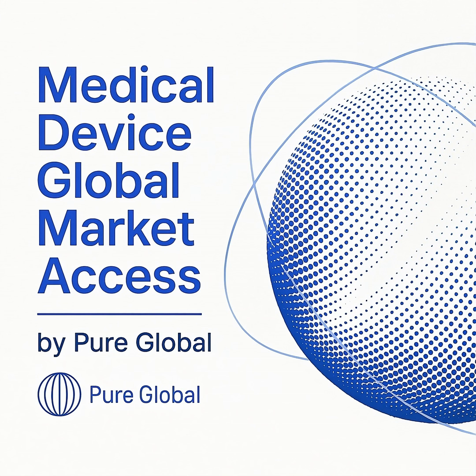Today we are focusing on a critical standard for any medical device manufacturer conducting human trials. ISO 14155-2020, which outlines the principles of good clinical practice, or GCP, for the clinical investigation of medical devices. This standard is fundamental for ensuring the ethical conduct of trials, protecting the rights and safety of human subjects, and generating scientifically valid clinical data that is accepted by regulatory bodies worldwide, including those in the European Union and the United States. The 2020 version, published in July 2020, represents a significant evolution from its predecessor.